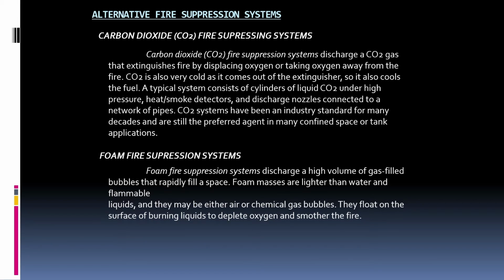CO2 systems have been an industry standard for many decades and are still the preferred agent in many confined space or tank applications. The principal problem with CO2 is that it must be used in fairly high concentrations, and because high CO2 concentrations deplete much of the oxygen in a space, this type of system cannot be used with occupants or other living beings present. As a result, it is usually used in confined areas such as mechanical chases, unventilated areas, and display cases.